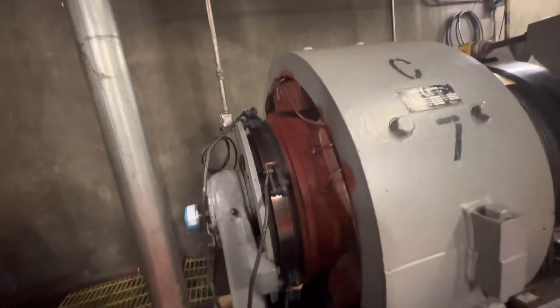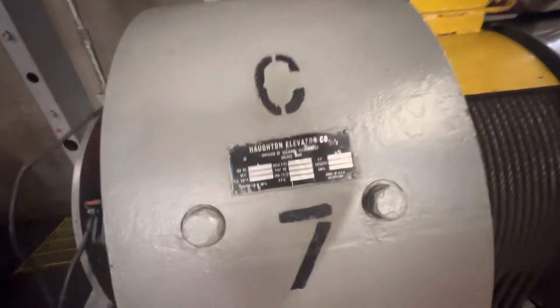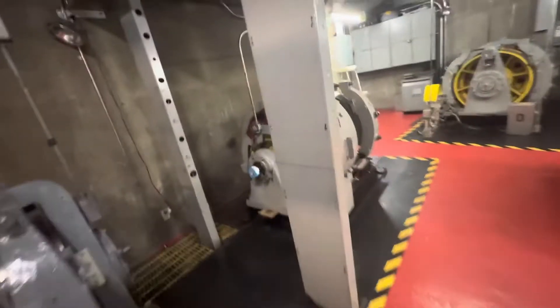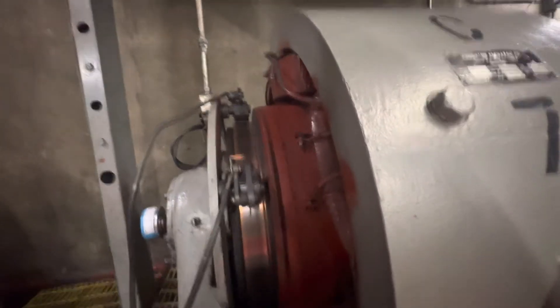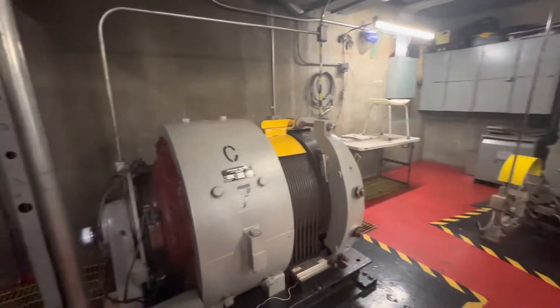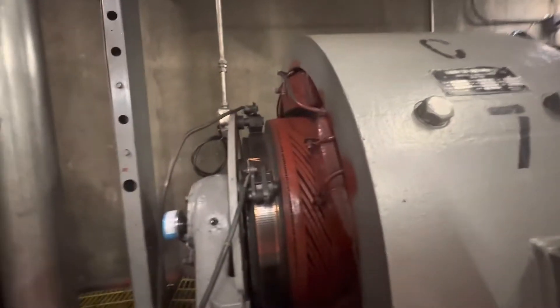That commutator really badly needs sanding. That needs sanding — that commutator needs sanding. 51 horsepower, 1971 — that's your date. That commutator's fine, but this one is arcing. Look at that — right there is your issue. And that's carbon filled up all over it. You definitely need this sanding.